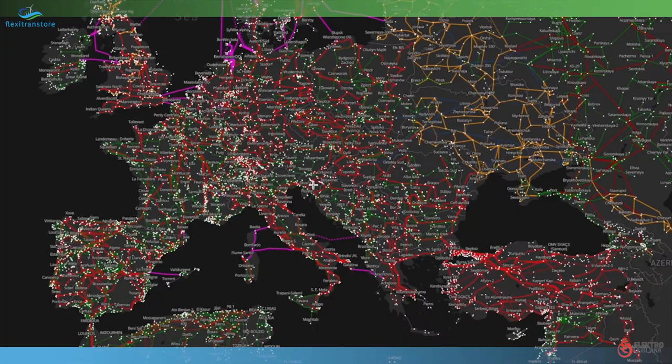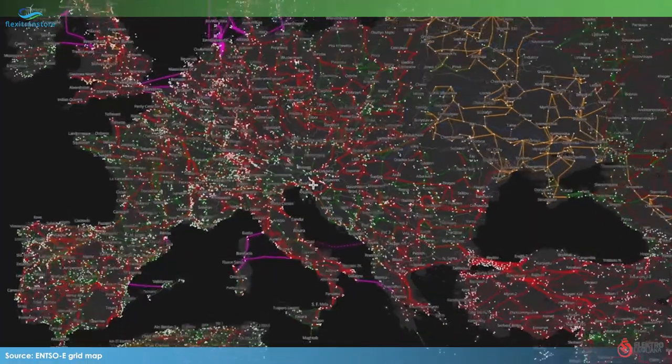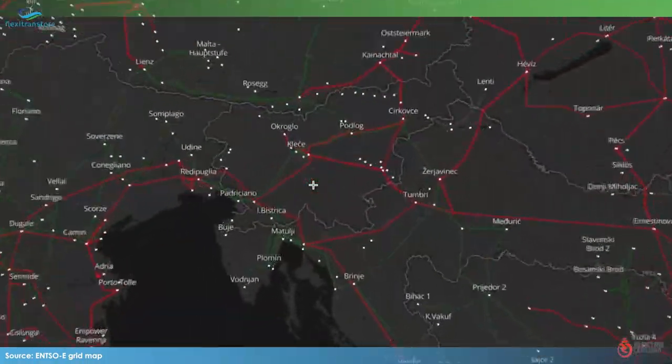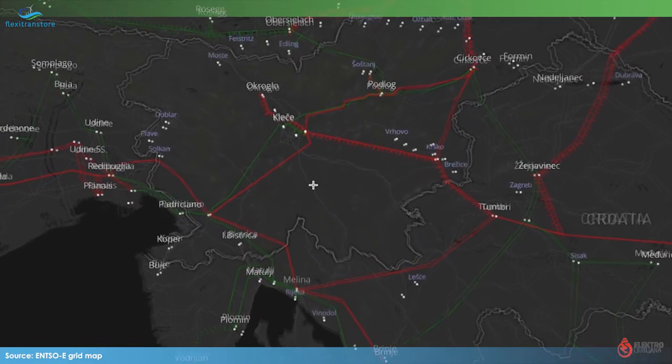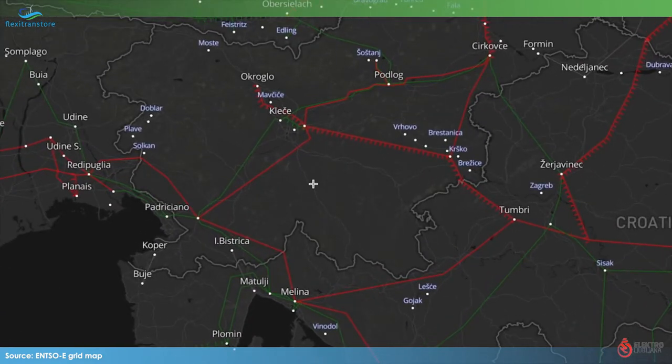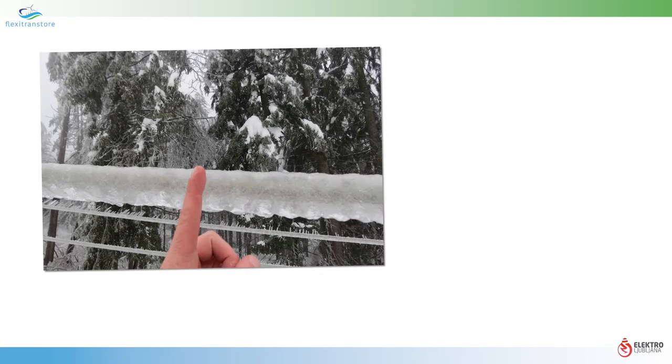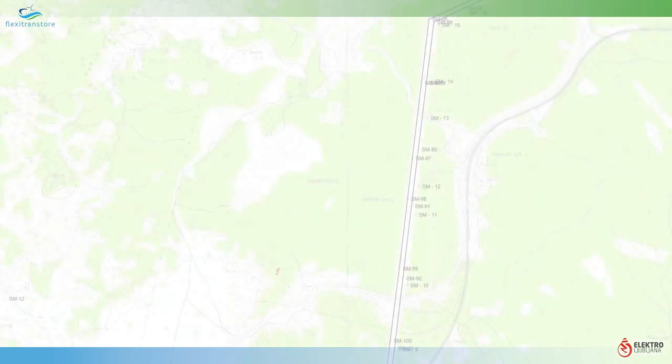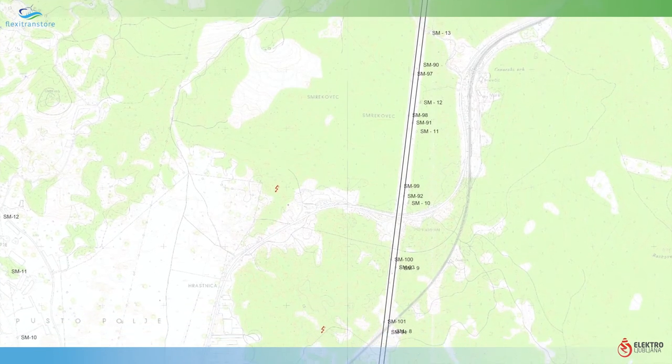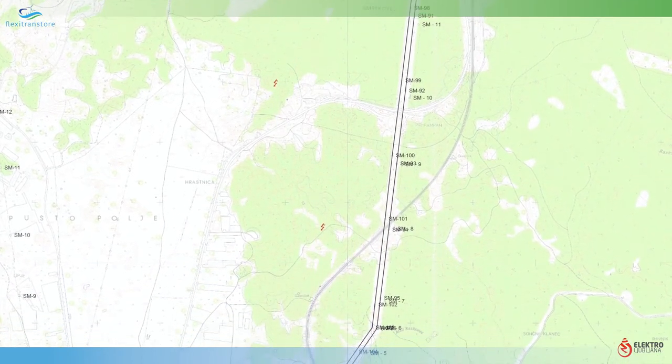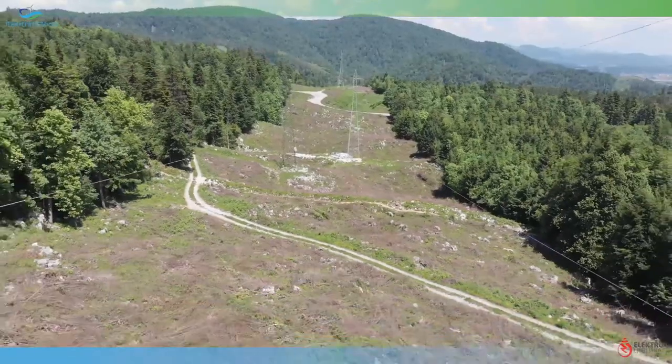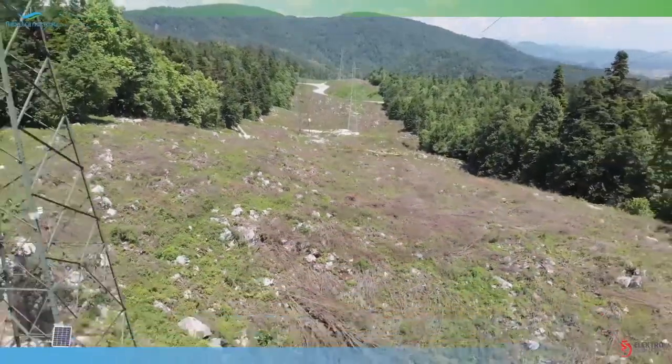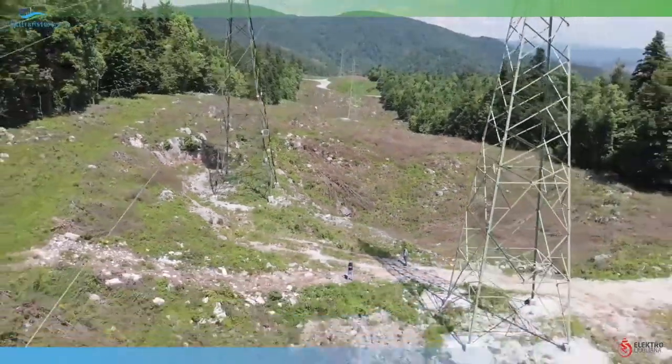The focus of the project is on the Kleče Logatec 110 kV line, which plays an important role in the Slovenian electricity system. It is responsible for energy transfer between Jumena and the middle of the country. There was an icing event in 2014, which caused several towers of this power line to collapse. Redispatching actions and ampacity control are possible on this line, which facilitate the prevention of icing events. The Kleče Logatec line seemed to be a good choice for demonstration activities.